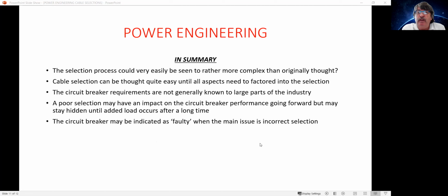The idea here is to give you some additional information so that you think a little bit deeper into the situation that may occur. It may in fact result in an application down the line where you actually say the circuit breaker is faulty. Being in that game for many years, you do get a lot of people who always claim the circuit breaker is the thing that's not working, when a poor selection, or a selection that doesn't take all accountable issues into account, hasn't been done correctly. And we do see this. The biggest number of circuit breakers in the world are thermal type. They by far outweigh all the other technologies at this time.